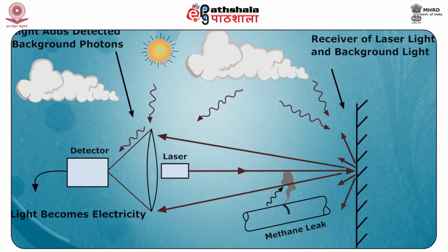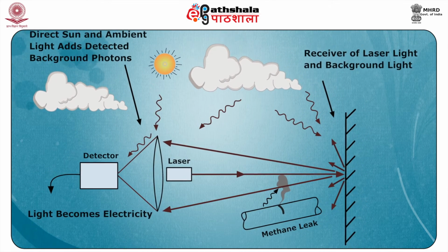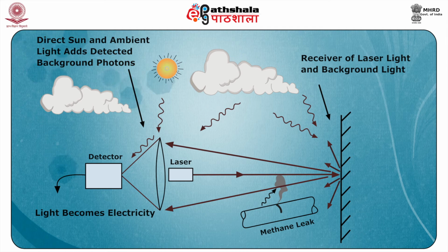It is an open path infrared detector and can scan a wide area. It is used for detecting gas leaks from a distance. Therefore, it is widely used to inspect areas such as processing plants, storage tanks, overhead rack mounted piping, and compressor stations.